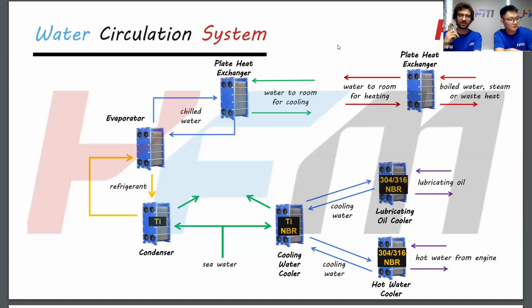The condenser is going to be titanium, regarding the gaskets I'll talk about that very soon. The evaporator is also going to be stainless steel. And the remaining plate heat exchangers are going to be stainless steel with NBR and EPDM, in the case of the one for water for room cooling, and the water for room heating is going to be EPDM.